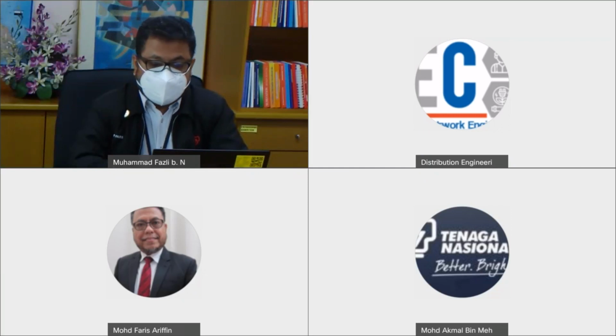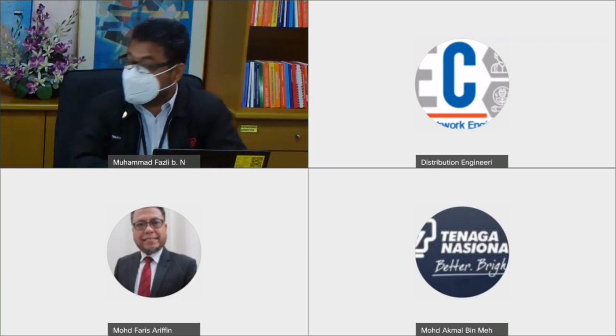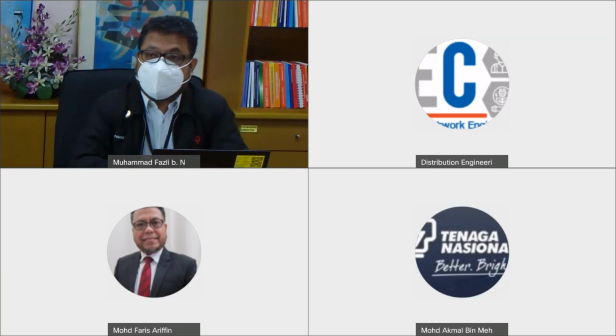Yes, the tower footing resistance. Okay, for 33 kV it's also similar, because we have the shielded and unshielded, and also poles with equipment. For poles with equipment, we need to ensure that the tower footing resistance or pole footing resistance is less than 3 ohms. For a shielded system, it needs to be below 10 ohms. And for unshielded with the use of a wooden cross arm, for example, we have to ensure that the pole footing resistance or tower footing resistance is below 15 ohms.